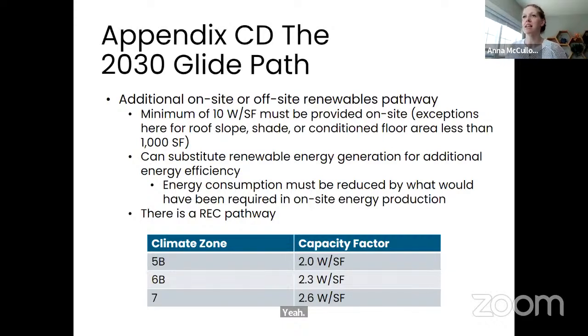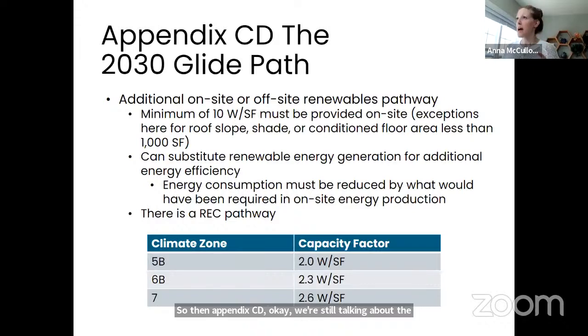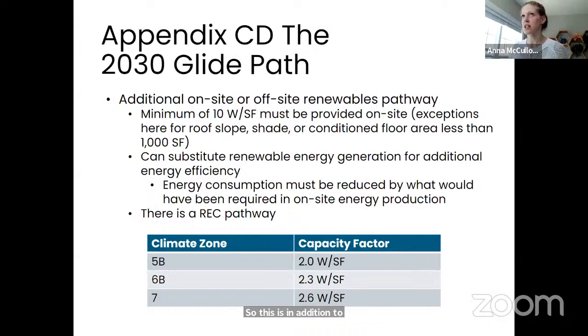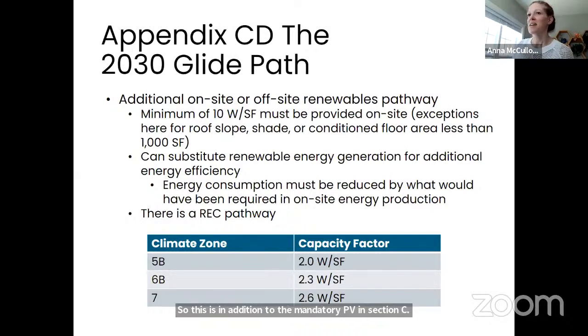So in Appendix CD, we're still talking about the glide path. The other pathway is additional on-site or off-site renewables, in addition to the mandatory PV in section C405.15. You have to provide this additional capacity factor: for climate zone 5B, 2.0 watts per square foot; 6B is 2.3 watts per square foot; and climate zone 7 is 2.6 watts per square foot. You have to provide a minimum of 10 watts per square foot on site.